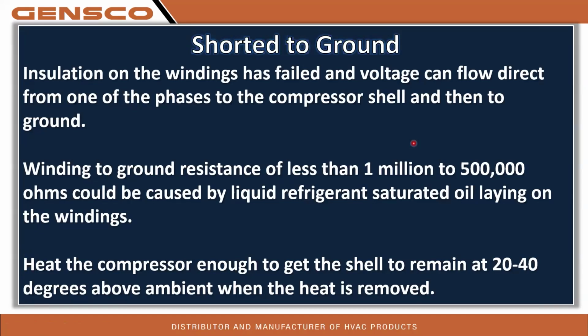So shorted to ground. Insulation on the windings has failed, and voltage can flow direct from one of the phases to the compressor shell and then to ground, or winding to ground resistance less than 500,000 ohms, which could be caused by liquid refrigerant saturated oil laying on the windings. That's why you have to heat it up. If you actually look in the install manual for a lot of the units, it will tell you to meg ohm the compressor before running. And if the resistance is less than 1 million ohms, to heat the compressor again and meg ohm test the compressor. It's actually in the install manual. You have to heat the compressor enough to get the shell to stay 20 to 40 degrees above ambient temperature when the heat is removed.